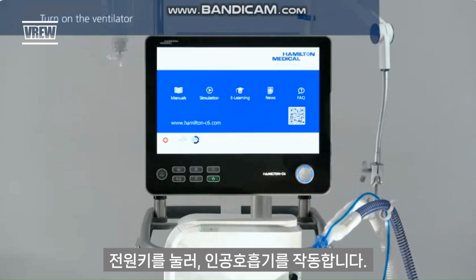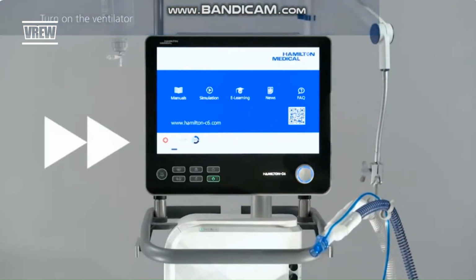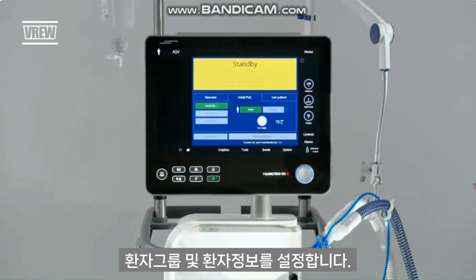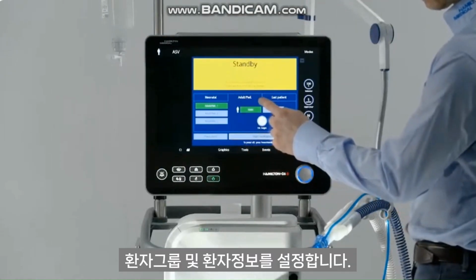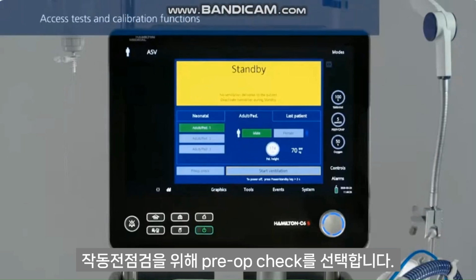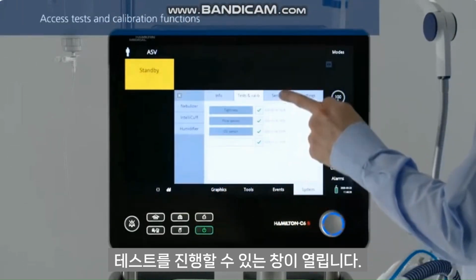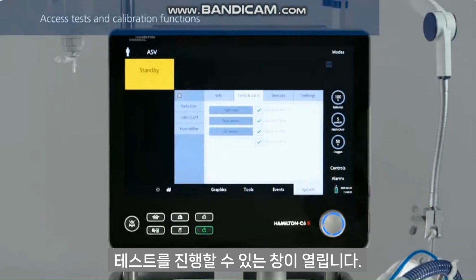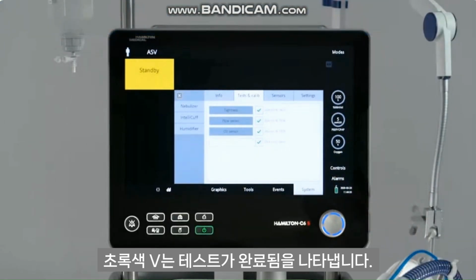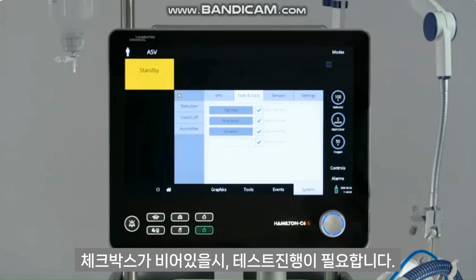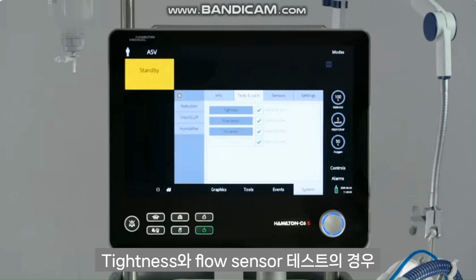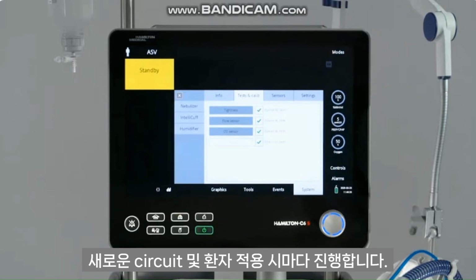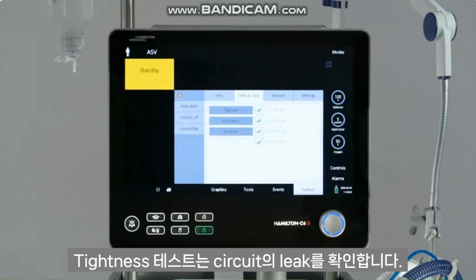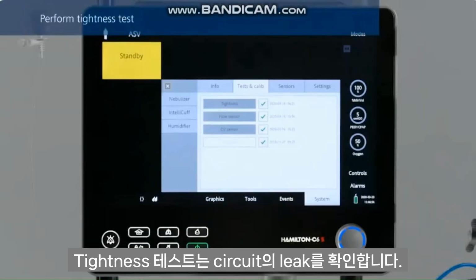The ventilator runs a self-test. When that is complete, select the correct patient group. To access tests and calibration functions, touch Preop Check in the standby window. The tests and calibration window opens. A green check mark indicates the component is calibrated and ready, while a red X indicates the last calibration was unsuccessful. A box with no marks indicates the test or calibration has not been performed. Perform a tightness test and flow sensor calibration each time you have connected a new breathing circuit or component, including a flow sensor. The tightness test checks for leakage in the patient breathing circuit.